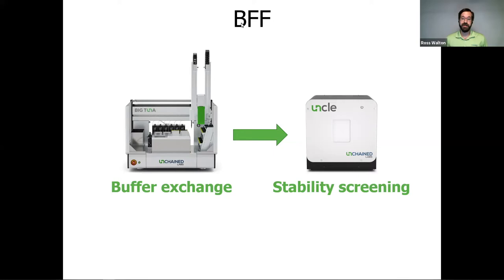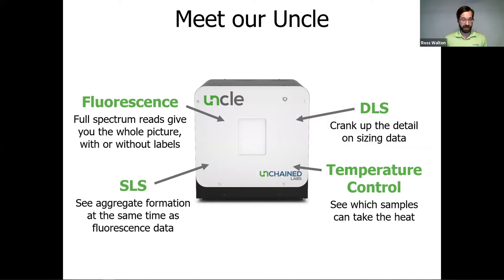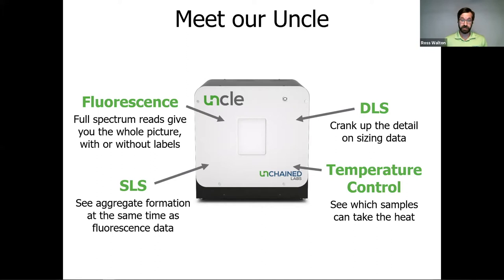I'm Ross Walton, one of the application scientists here at Unchained Labs. UNCLE is an all-in-one multimodal stability platform that contains two different lasers: a 266 nm laser and a 473 nm laser. The 266 nm laser is ideal for looking at capsid protein stability using intrinsic fluorescence, while the 473 nm laser can excite a variety of fluorescent dyes, including DNA-sensitive dyes like SYBR Gold. UNCLE also reads full-spectrum fluorescence, so you get the whole picture of your AAV capsid and its thermal stability — with or without labels, depending on what you need.